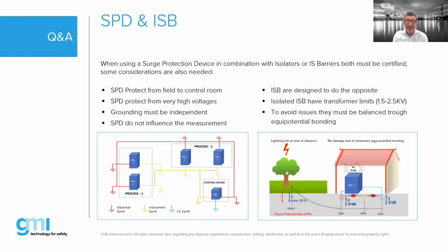And the grounding must be independent. If you're using a Zener barrier, you cannot ground the Zener barrier to the same ground you ground your SPD to, correct, Bob? Correct, as we discussed earlier. And now the question was about the grounding problem, and I understand that the way to avoid that for all the SPDs is to have unipotential connection of these grounds. So they have to be equipotential, the bonding. There's a way to connect your SPD to the same ground, making the ground equipotential, so you avoid any loop issues.